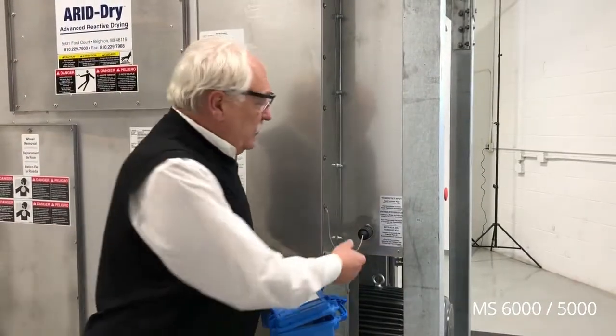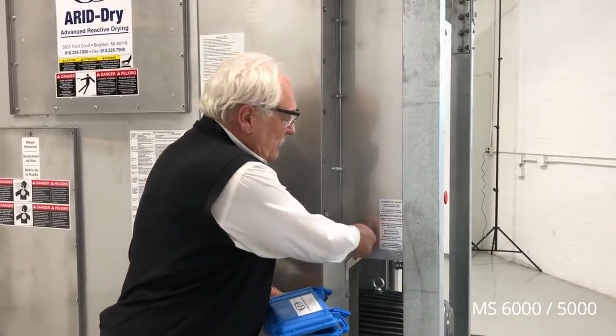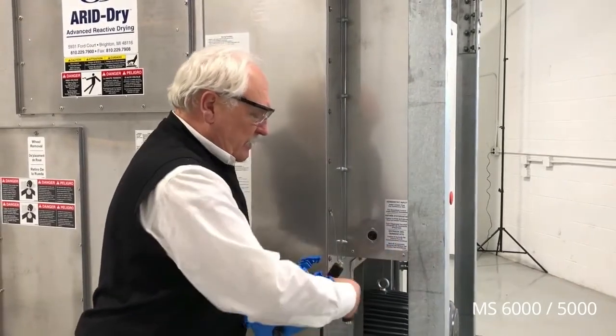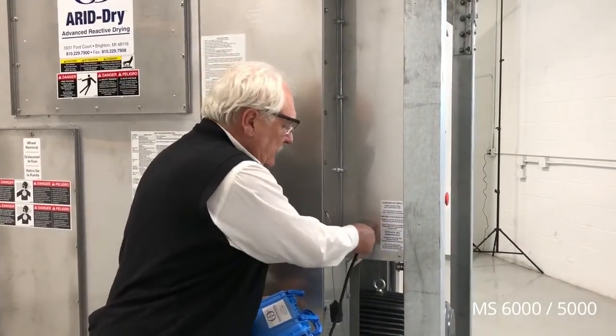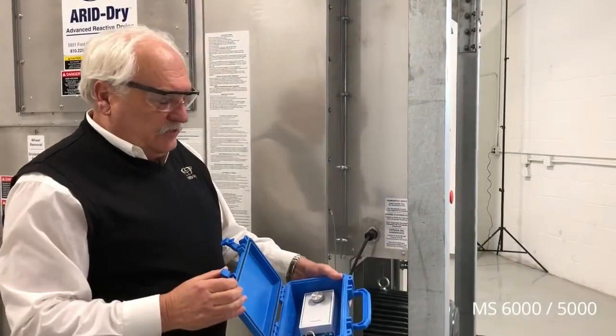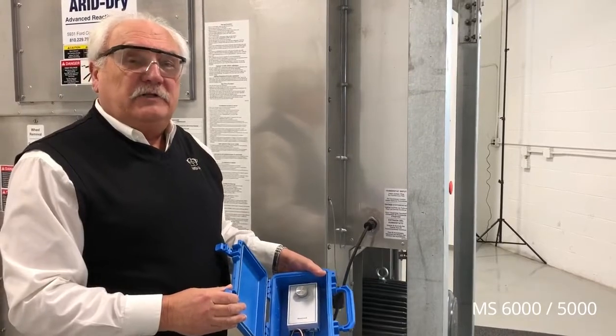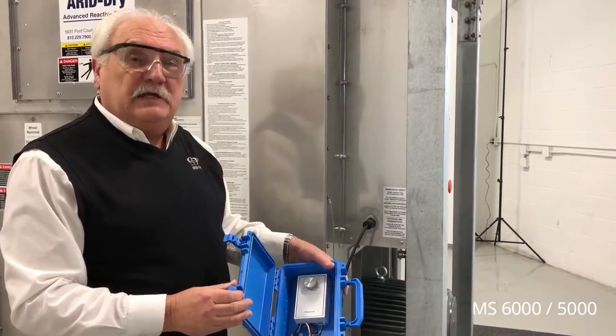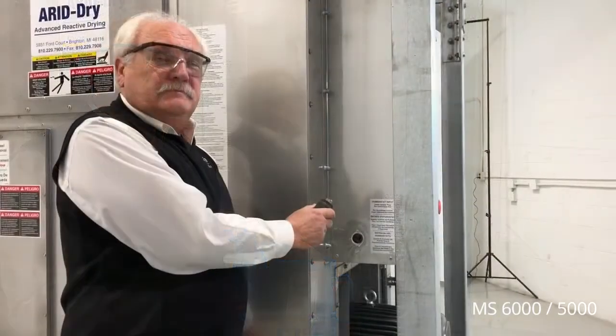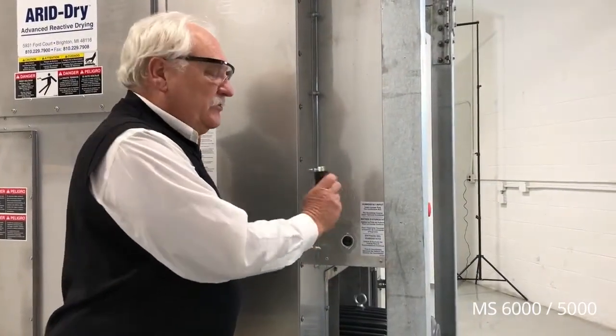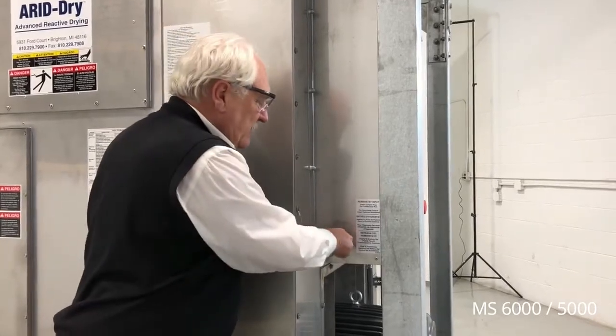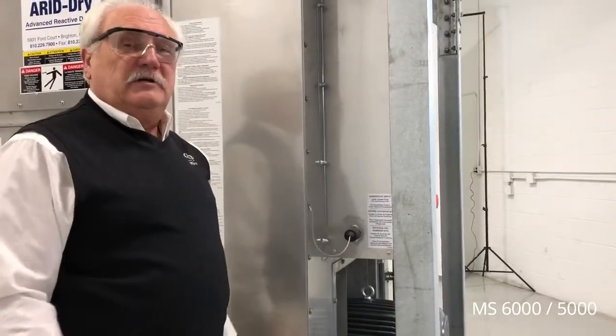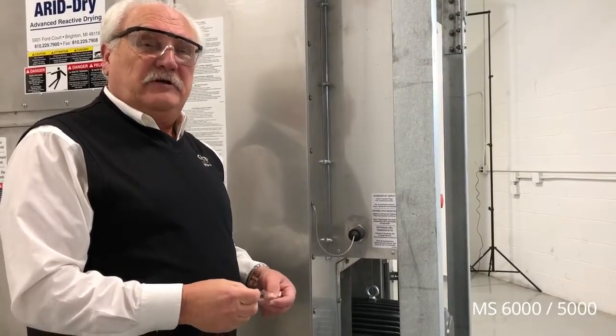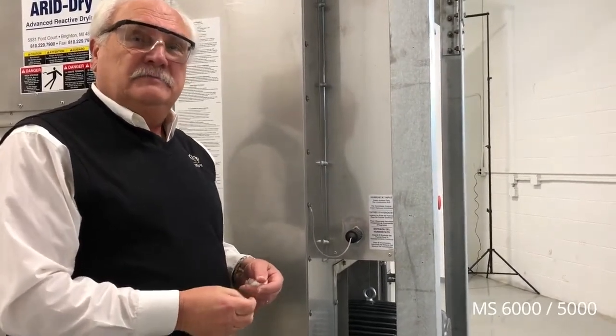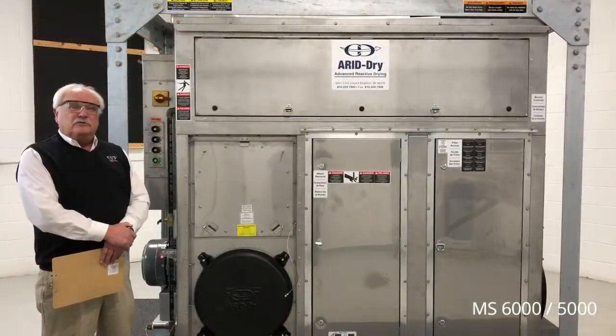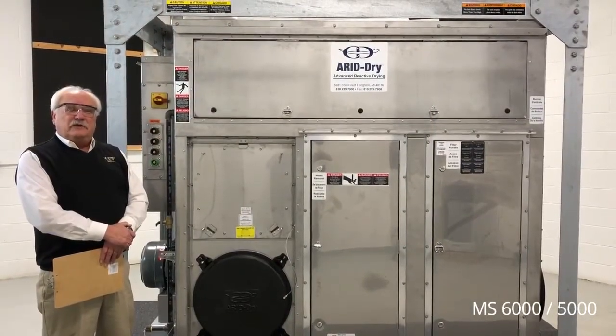The unit is equipped with a RemoteHumidistat capable plug. To use, you remove the jumper plug and plug in a RemoteHumidistat cable, and then the circuit is energized or de-energized by the relative humidity reading on the dehumidistat. When starting the unit, always make sure that the RemoteHumidistat plug is in and locked. This plug is a circuit jumper to allow the dehumidifier to operate 100% of the time. This concludes the tour of the MS6000/5000 RC2.